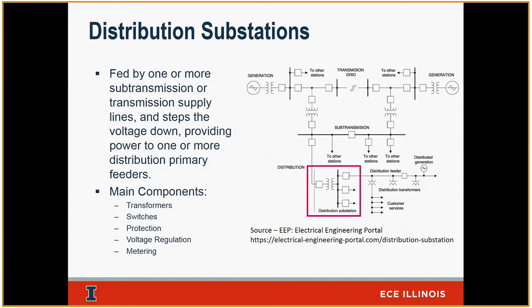Our transformers here inside the substation are stepping the voltage down. So if this was 69 on the high side, typically what we have at Ameren is 12.47 or 13.2 kV. The difference in these voltage levels is really due to the legacy companies that came together to form Ameren. In Illinois Power's world, their engineers and their philosophy decided to have all their voltage levels at 12.47. The other legacy company had 13.2 kV, but it's just a different way of running the distribution system.